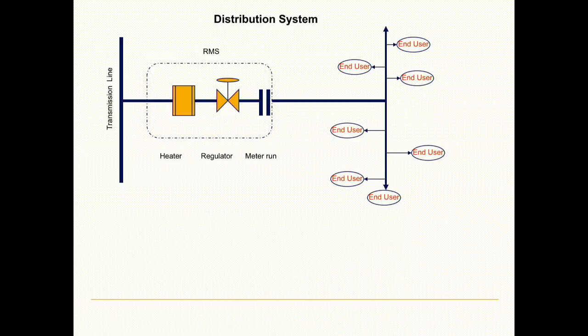Now the distribution system. Typically, a distribution system looks like this - this is the high pressure line, let's say the pipeline coming from Atuabo to Takoradi. It's at high pressure, but when it's used, it's usually at a much lower pressure, so they have to regulate the pressure down and meter it before it can be used by the end user. More importantly, you usually need a heater, because once it goes through regulation, the temperature drops due to the Joule-Thomson effect - a temperature drop accompanies the pressure drop.